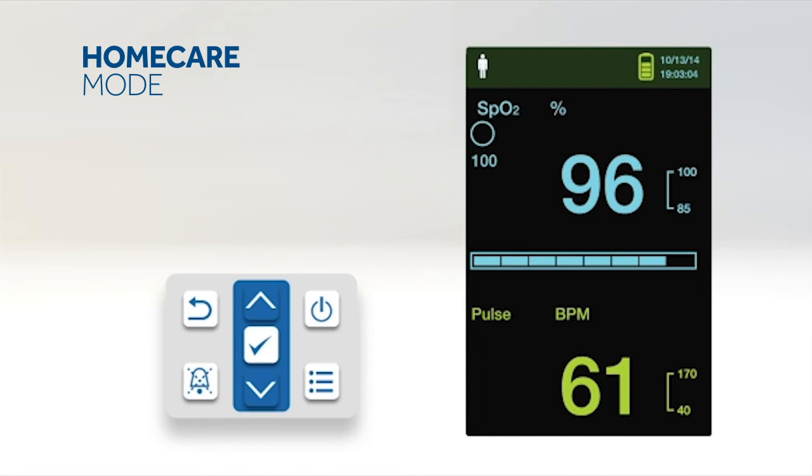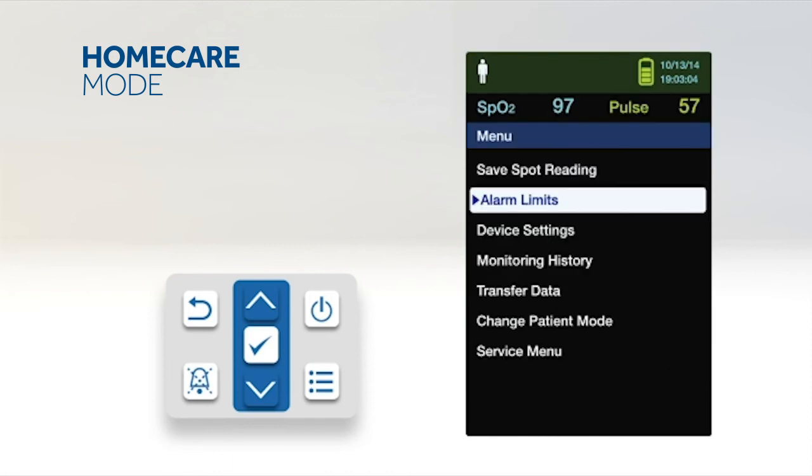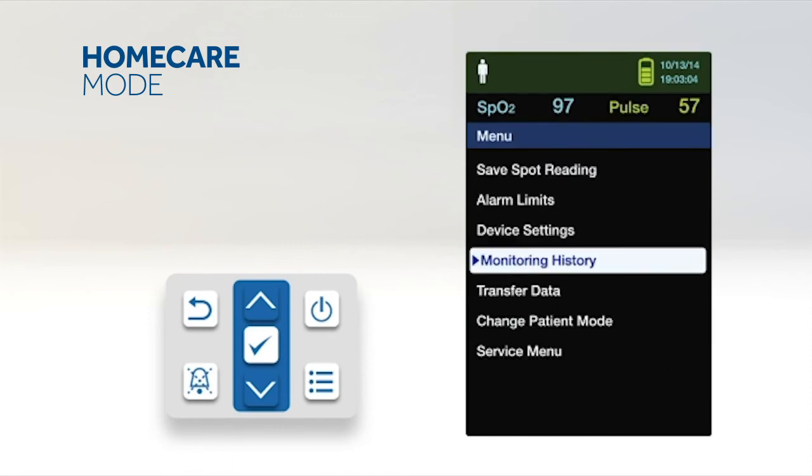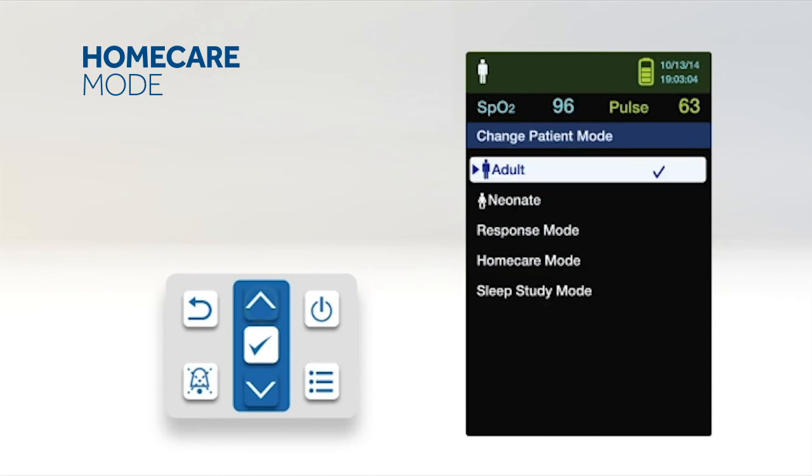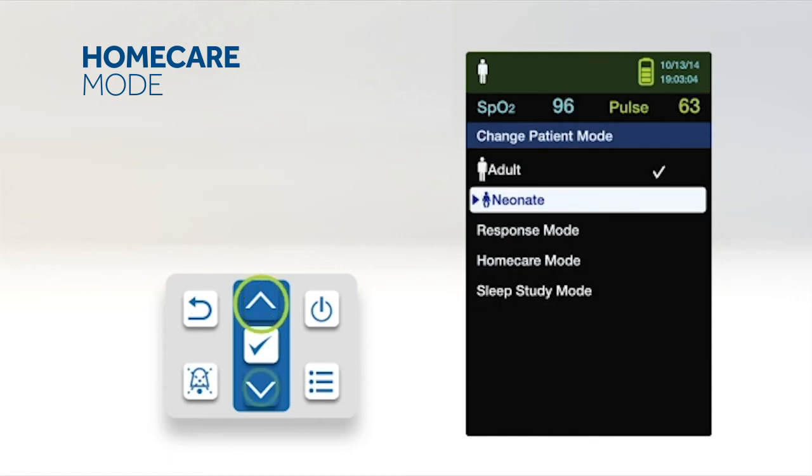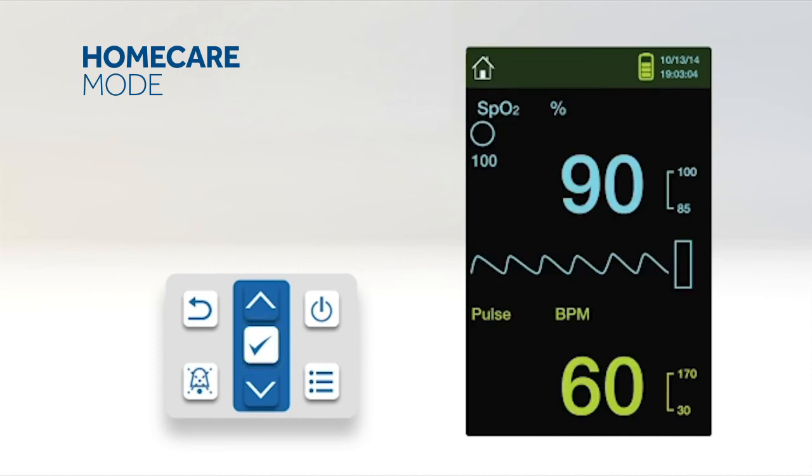When using the monitor outside of the hospital environment, set the monitoring system to Home Care Mode. To set Home Care Mode, access the Change Patient Mode menu, press the up or down button to highlight the Home Care Mode menu, press the OK button to select Home Care Mode. The monitoring system is now operating in Home Care Mode.